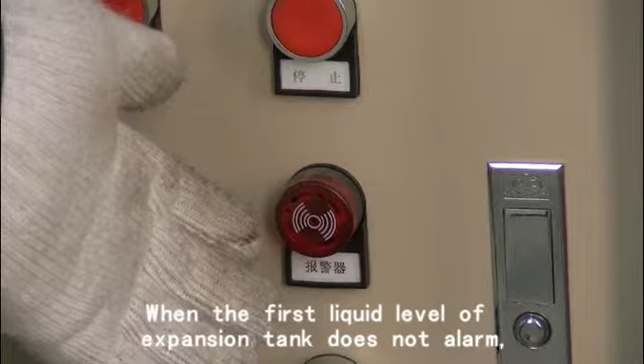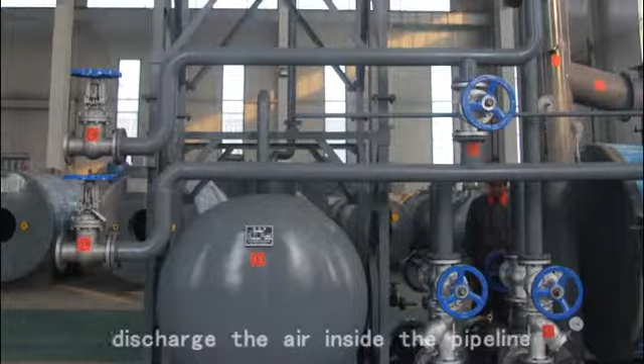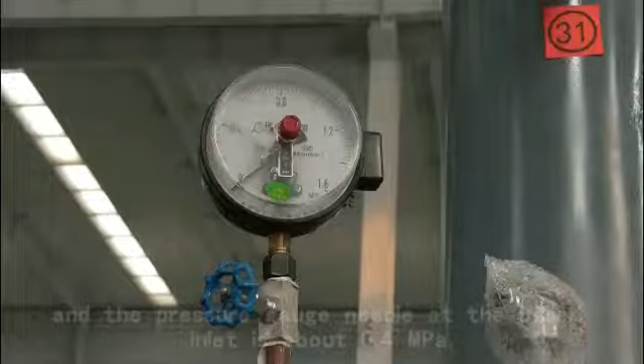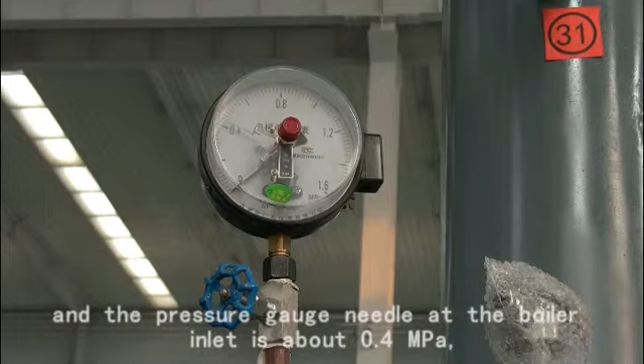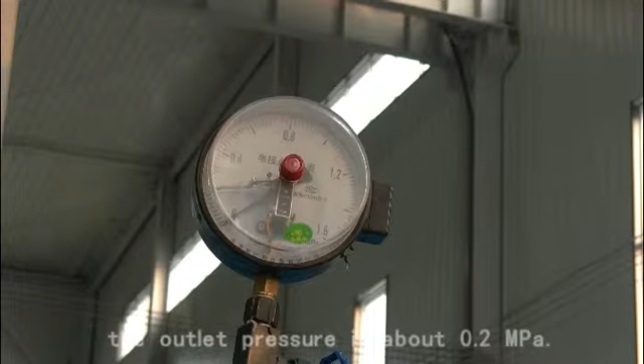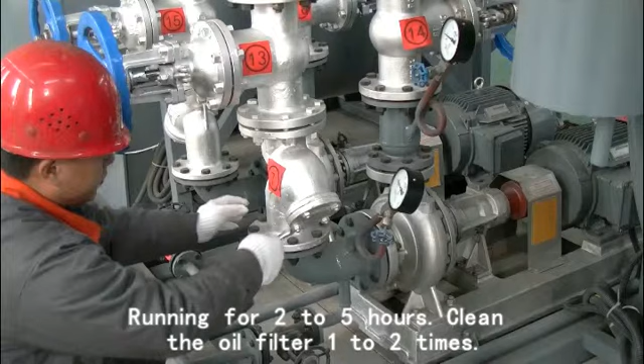When the first liquid level of the expansion tank does not alarm, start the first circulation oil pump and inflate cold oil circulation. Discharge the air inside the pipeline until the first liquid level of the expansion tank does not alarm, and the pressure gauge needle at the boiler inlet is about 0.4 MPa and the outlet pressure is about 0.2 MPa. Running for 2 to 5 hours. Clean the oil filter 1 to 2 times.